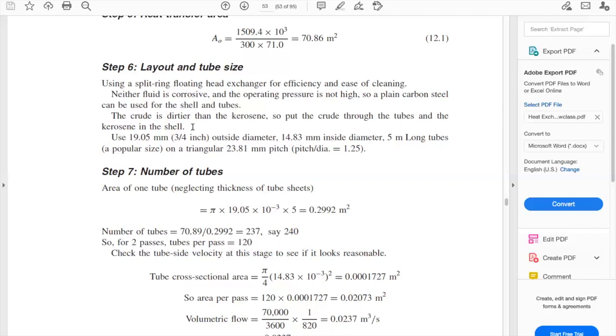The dirtier fluid, which is the crude, goes through the tubes. We use 19.05 mm (3/4 inch) outside diameter, 14.83 mm inside diameter, 5-meter long tubes. Why? Because this is a popular size, meaning it is readily available. That is the logic behind choosing this tube size.